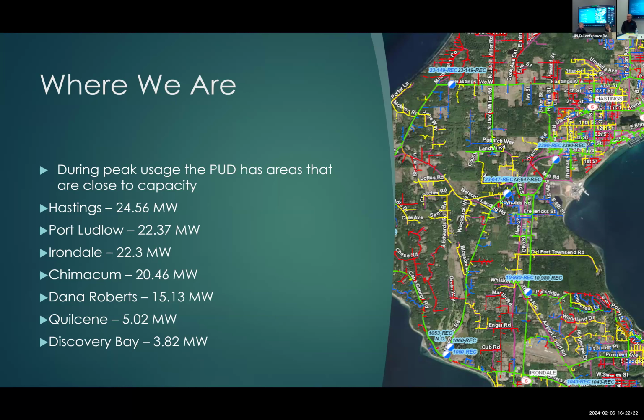Yes, okay, so we can see if our voltage is dropping below what it should be. Not only if it's dropping, but during cold load pickup, we can see what the instantaneous demand is per house, which has given us a lot of useful information that gets relayed back to our engineers, who are starting to do load flow studies per feeder.